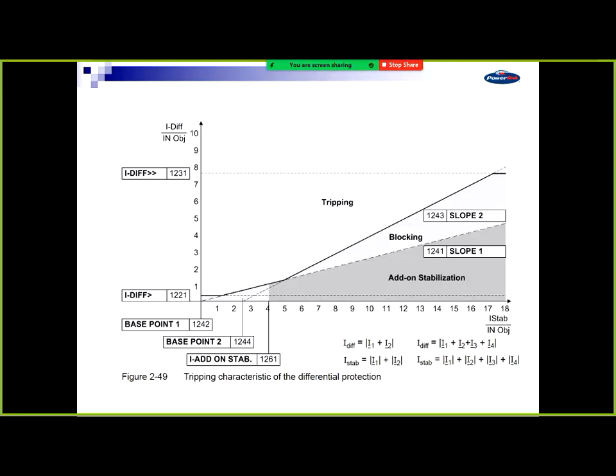And what happens is that line going up at an angle that's getting bigger. So you need more differential current to trip as your stabilise, they call it, but as your bias current gets higher, you need more differential current. So if your errors are increasing, it's compensating for that. It means that it really does need to be a lot. So it helps with your errors and your CTs happening, that you don't get an external fault causing an unbalance in your bias diff to trip.